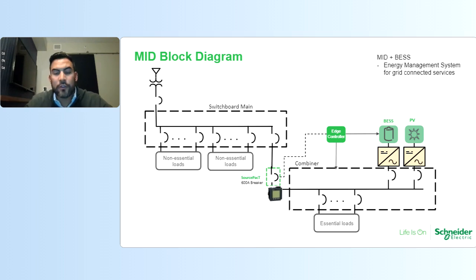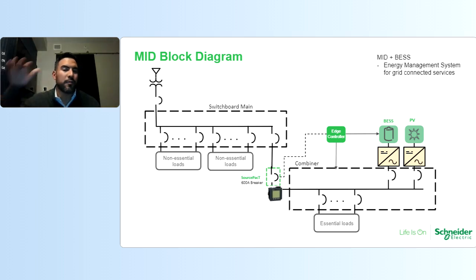And if you want to take advantage of the grid connected services, you still require some type of energy management or cloud service. And again, that could be provided through Schneider or someone else, but you will also need that supervisory network to oversee your entire microgrid system. And that mainly entails, again, taking advantage of time of use rates, peak shaving, self-consumption. If it's a sunny day and you're producing a lot of PV, have the availability to curtail PV production. That all comes through that supervisory energy management platform, which can be provided by Schneider or, again, a third party.